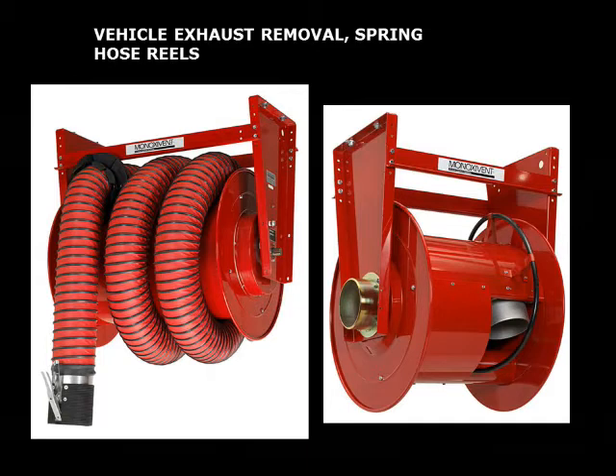Now, I want that hose reel tailpipe to stop recoiling when it's about 6 feet above finished floor. The reason for that is it allows the average person to be able to reach it, because you must reach it to pull it down and utilize it. So the concern would be if we're installed at 13 feet, this hose stop is going to be positioned at a certain point on this hose.